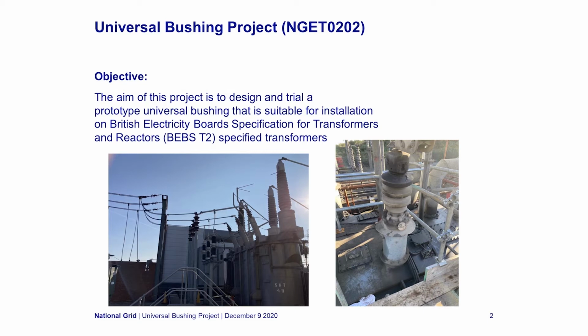However, holding, say, 3 bushings for each transformer design requires significant financial investment in stock that is turned over only very occasionally, when the number of transformers of each design is fairly small. In addition, beyond the capital cost, spare bushings need testing and recertification every 7 years. We wanted to reduce our stock holding of 33 kV bushings by having a single design that could be installed on all transformers which were supplied to BEBS T2, a specification for transformers that was in place across the CEGB and still in use until the 1990s.